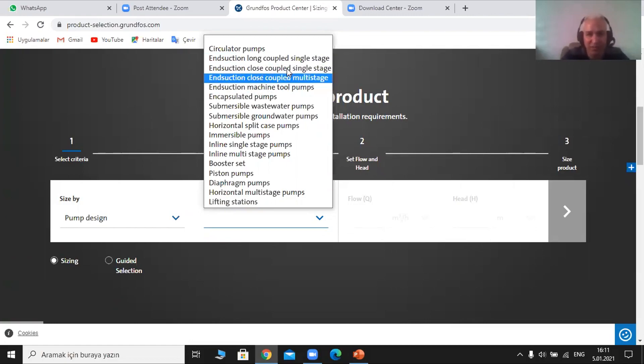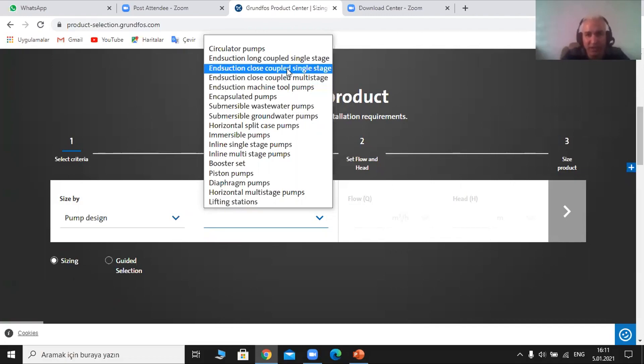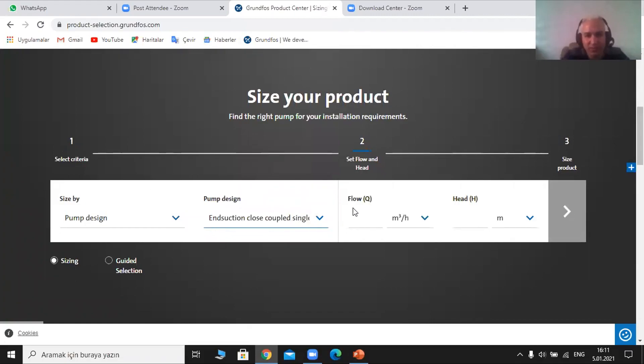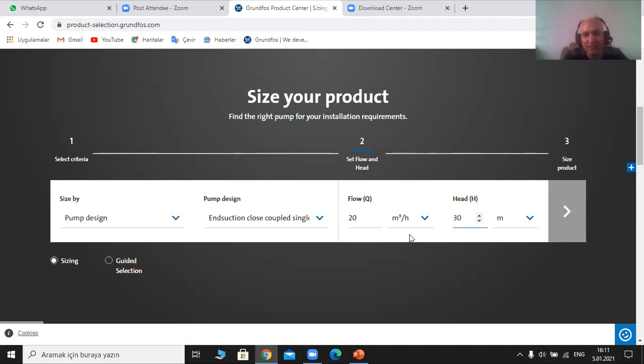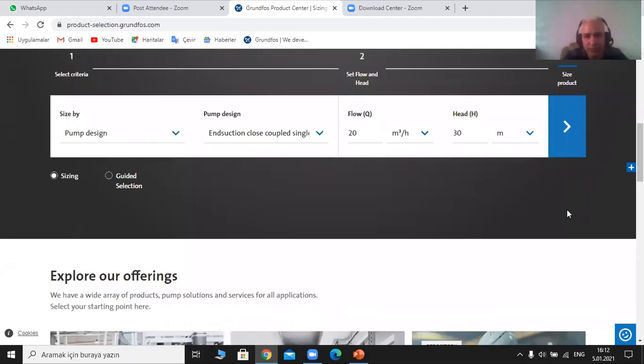If you go through the past sessions, you can see the difference between the names. Let's choose end suction close-coupled single stage. The flow rate: let's choose 20 cubic meters based on the range we are working on. And the head is 30. As for a single stage, the head shouldn't be over 40 to 50 as maximum. If we are going to increase the stages, you can reach even 200. But for single stage, it is preferable not to go over 50.